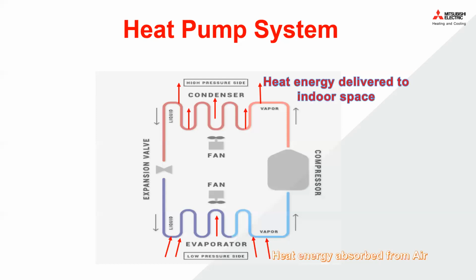Because refrigerants change state at negative 29 C at atmospheric pressure, by decreasing the pressure, we can cause vaporization or evaporation at very low temperatures, and thus absorb heat energy from very cold outside air. Another physics fact is that we have heat in the air down to absolute zero, which is negative 273 C. I've gotten a lot of questions of, you know, how is it able to grab heat from outside? Well, because there is heat in that air. We just don't feel it, but there's still heat that can be captured.